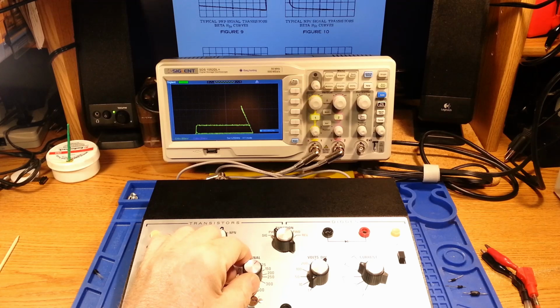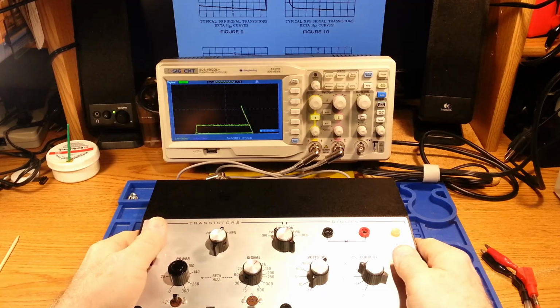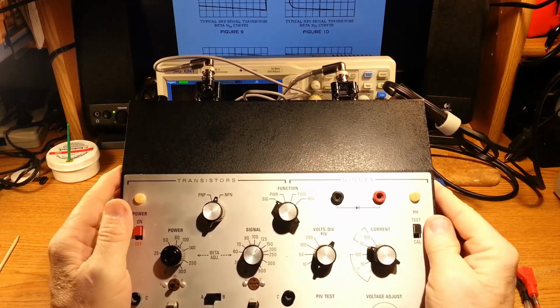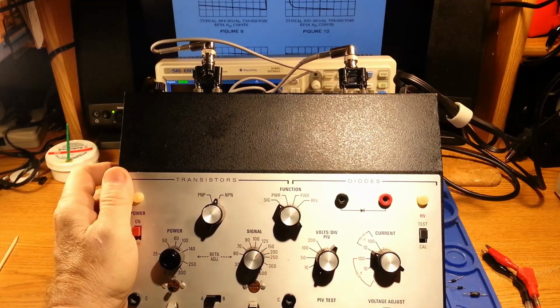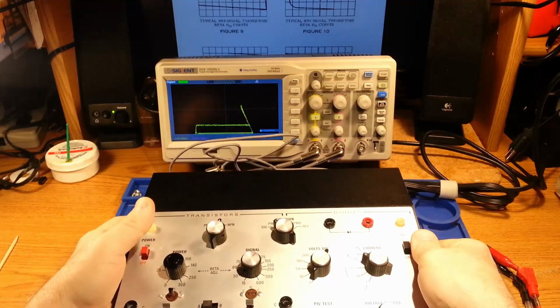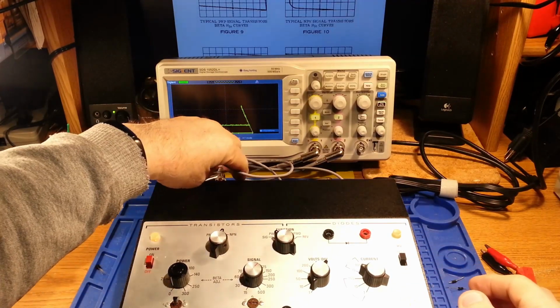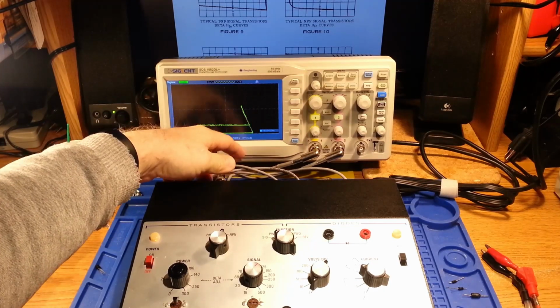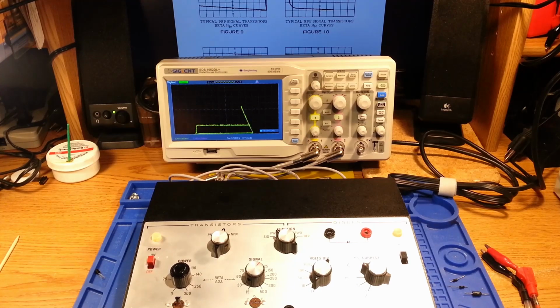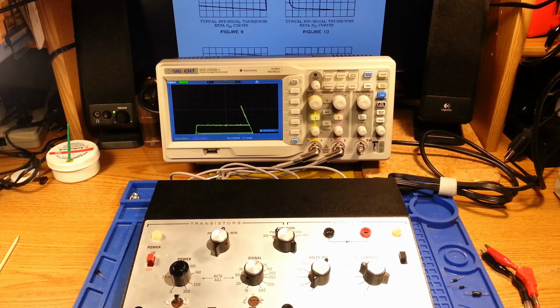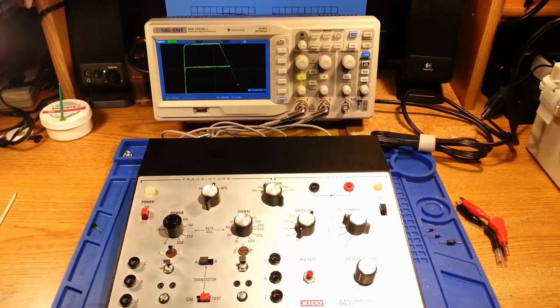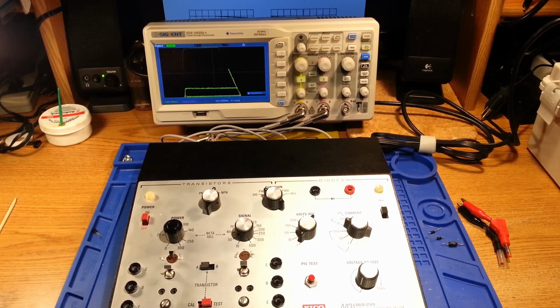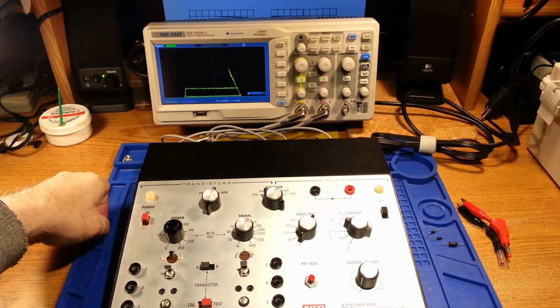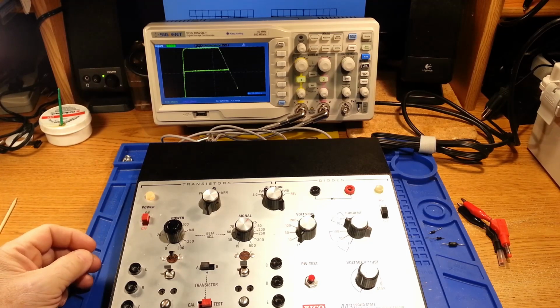And at this point, I am at 8 vertical centimeters of deflection, and my gain on the knob registers just over 125, if you could see it on the pointer. Like I said, this is not in any way, shape, or form a laboratory standard piece of test and evaluation equipment. It's a bench technician's tool to help troubleshoot and find parts that aren't behaving quite properly and eliminate them as part of the troubleshooting process.